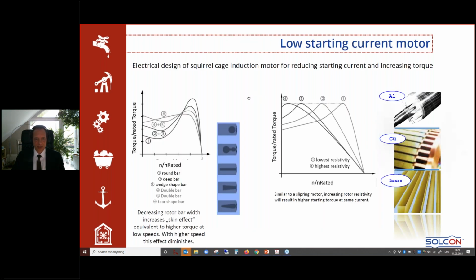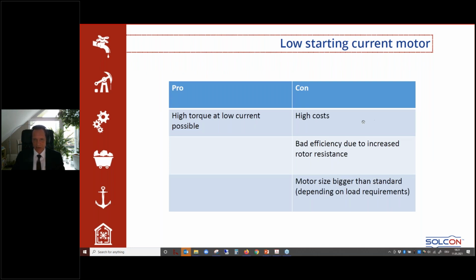You can increase the resistance in the rotor also by doing something in the motor rotor, either by the form of the motor rotor bars. And you see here with the different forms, you achieve different torque speed patterns, or you can increase the resistance of the rotor bars by applying different materials, going from aluminum, copper, special copper, or a certain brass. You can do this, but it means higher costs, and you have a bad efficiency due to the increased rotor resistance, which the motor sees all the time. And motor size is bigger than standard motors, sometimes double the size of a normal motor.